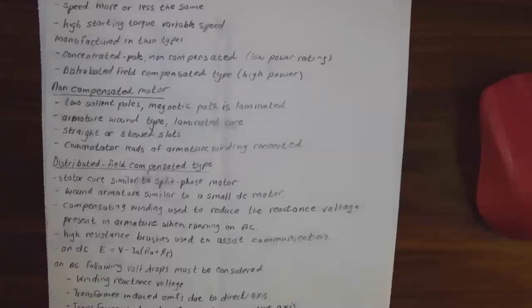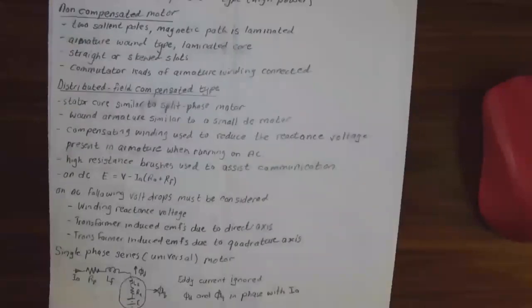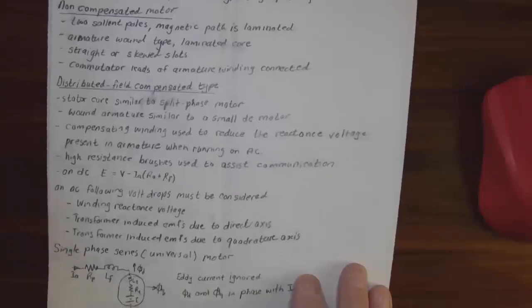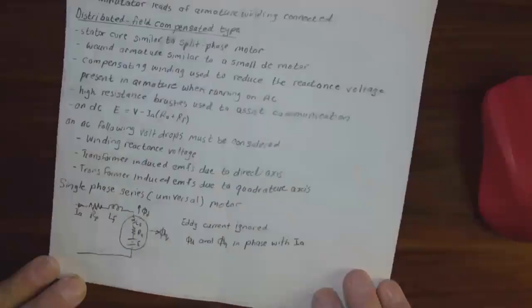The non-compensated motor has two salient poles, magnetic path is laminated, armature wound type, laminated core with straight or skewed slots. The distributed field compensated type has a stator core similar to a split phase motor, armature similar to a small DC motor. On AC, the following drops must be considered: winding reactance voltage, transformer induced EMF due to the direct axis and due to the quadrature axis.